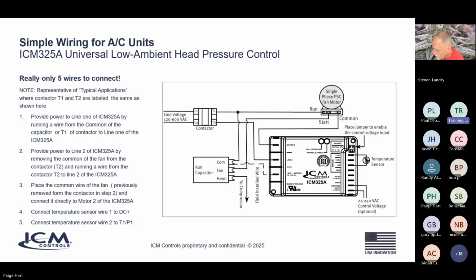And then the other 2 connections are just simply the temperature sensor, which go to T1, P1 and plus 5 volts. Please do not confuse it like many people do and put the sensor across T1 and T2. It doesn't go that way. You have to supply voltage to one side of the sensor. So plus 5 volts on one side of the sensor, and that's the temperature sensor, and then T1, P1 for the other side of the sensor. All right. And the pressure transducer will also have a wiring diagram on the installation guide.